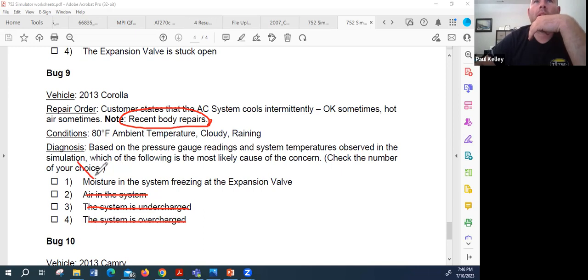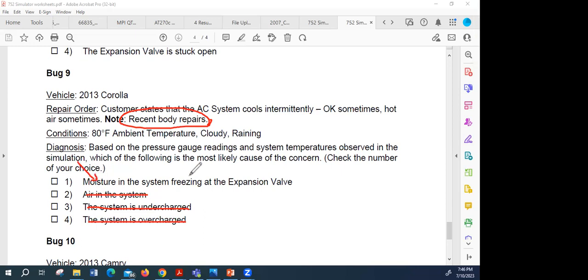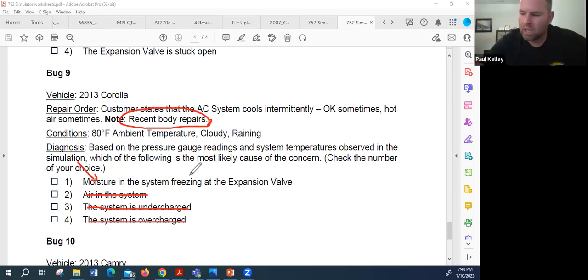Why would it be this one? Who can explain? Because when it freezes, it blocks the flow of refrigerant. Right, and this is one that I struggled with for a bit. If there's moisture inside the AC system, it's going to come around and hit that TXV. The TXV is going to be very cold, it'll freeze on the TXV, collect a bunch, and all that moisture is going to hit the TXV and become an ice blockage.